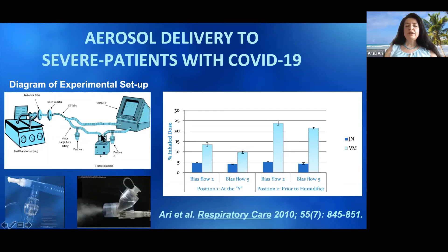As you can see from this figure, when we placed the nebulizer prior to the humidifier, we increased aerosol drug delivery to our patients. Inhaled dose was significantly higher than when we placed it at the Y. When we increased the bias flow from 2 liters per minute to 5 liters per minute, aerosol drug delivery decreased. So I would recommend using the nebulizer prior to the humidifier based on the findings of this study. And after our study was published, there were a couple other studies that evaluated similar parameters and they confirmed the findings of our research. Another study that was published in the guideline of the Chinese Medical Association was this one.